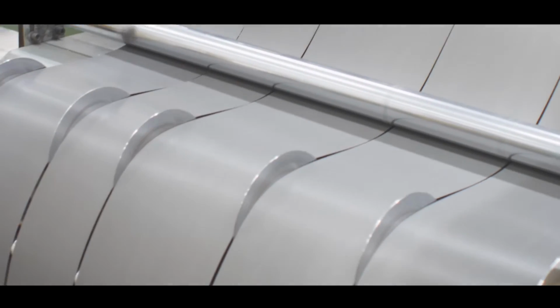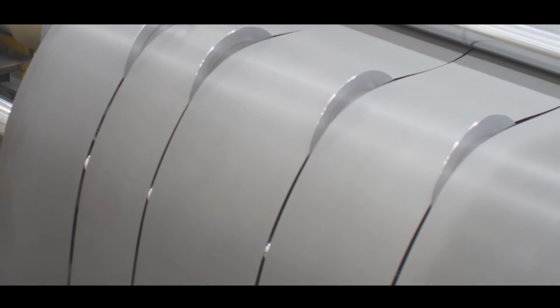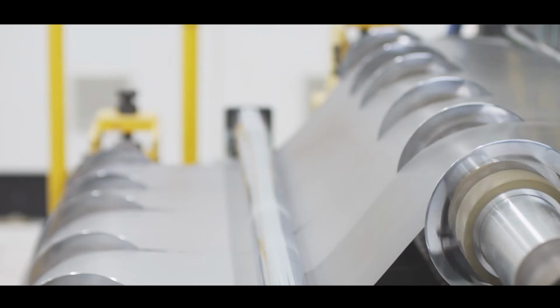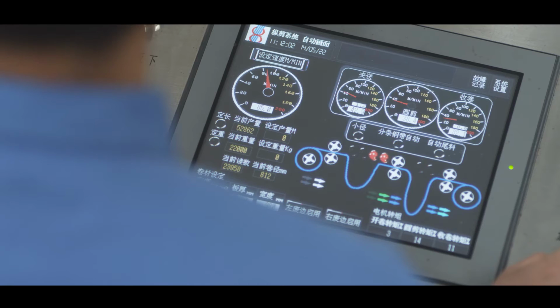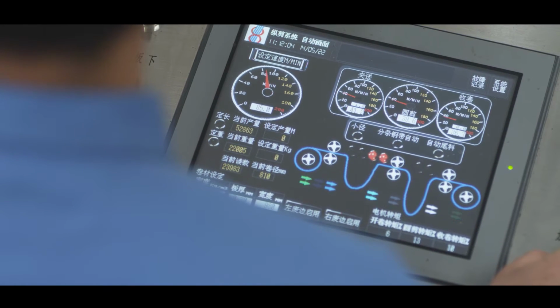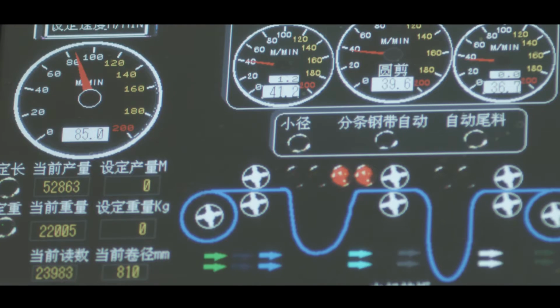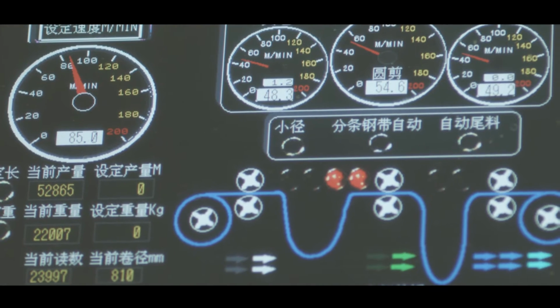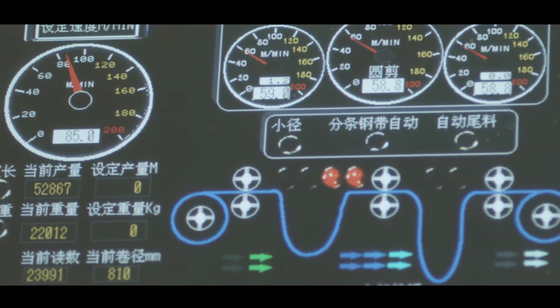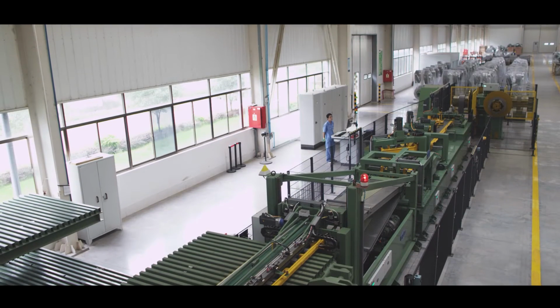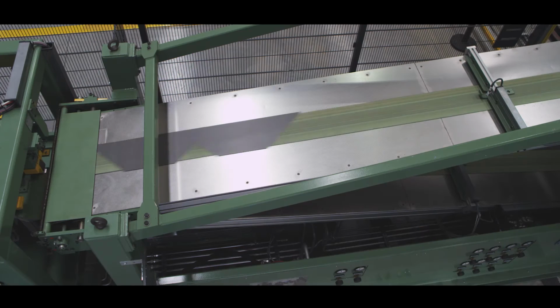It is for this reason JST utilizes core steel supplied directly from the mills, which undergo an advanced slitting process. This slitting process cuts the steel into strips with strict control on the strip width and tension as the strips are spooled to be used in fabricating the core laminates. Precision stamping equipment is used to cut the core laminates.